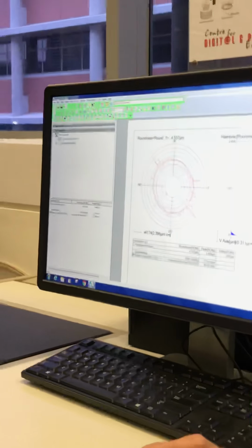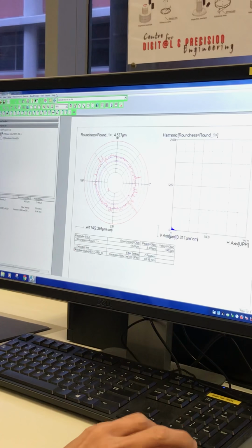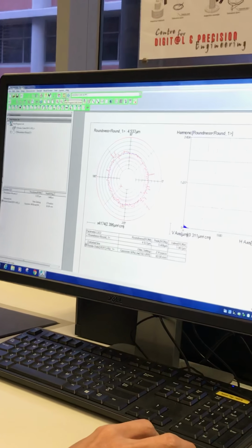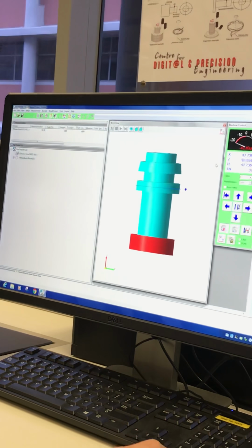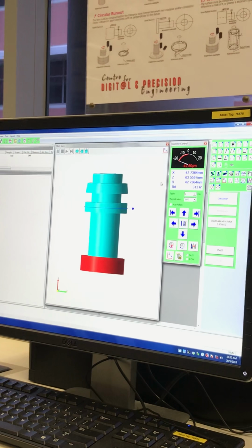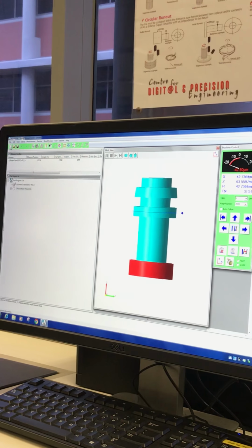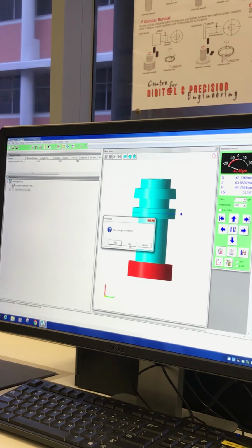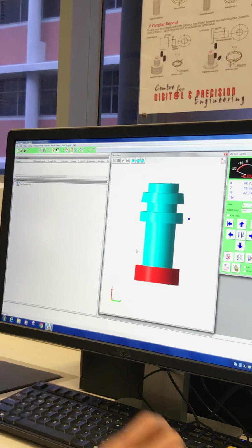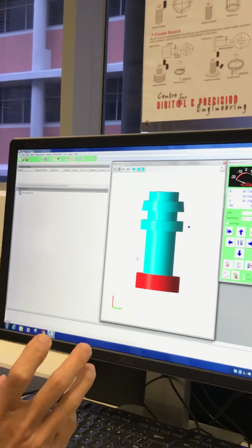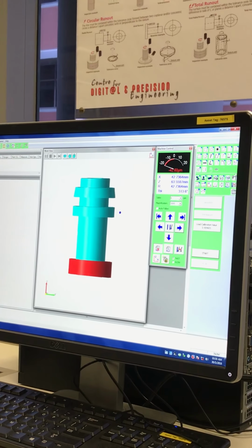Okay, next icon. What's supposed to be measured? What's the next step? You need to go back to the measure screen. Press PT. Very good. Okay, what is next? Open the new file here. Right click the concentricity icon. No need to save. Record down the result already, or if you want, you can print out the result. Okay, so concentricity, which one? Concentricity icon.